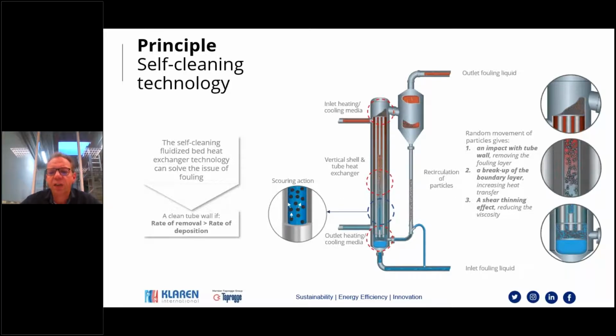On the other hand, we must say that we use lower velocities in the tubes than a normal conventional shell and tube. Meaning normally you would apply velocities between 2.5 and 3 meters per second for a normal design shell and tube. But in our case, we are below 1 meter per second. And this makes also that, of course, if you lower your velocity, your local heat transfer will reduce. But with the augmentation of the fluidized bed particles, you will see that we will get to the same level of heat transfer as for the conventional heat exchanger. But with one main advantage, that the heat transfer will remain constant over time.